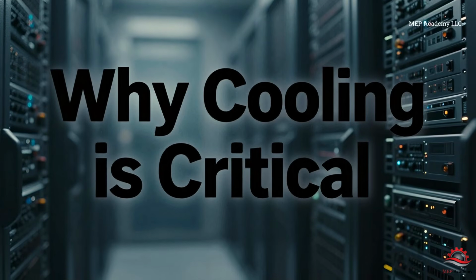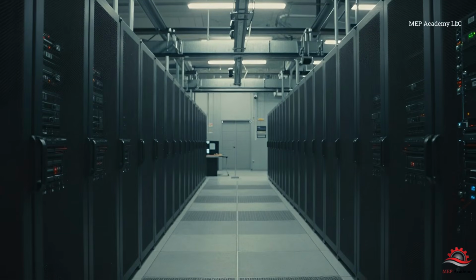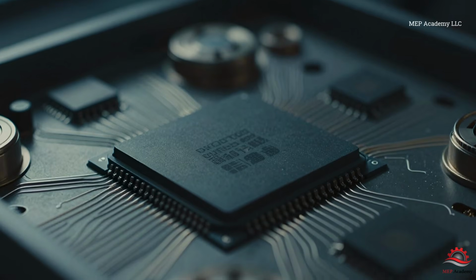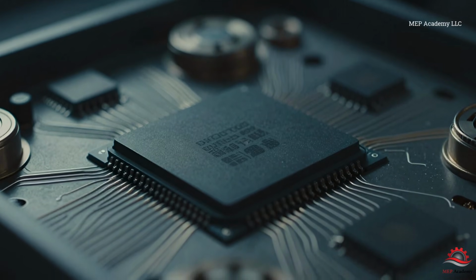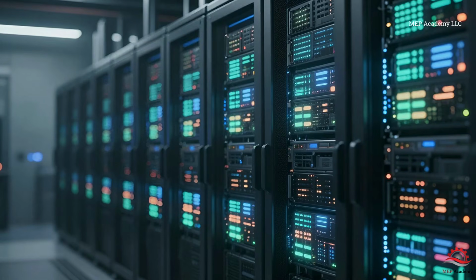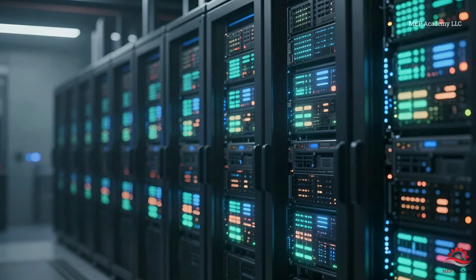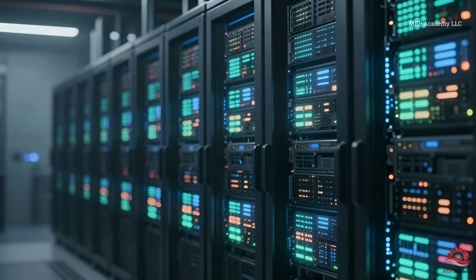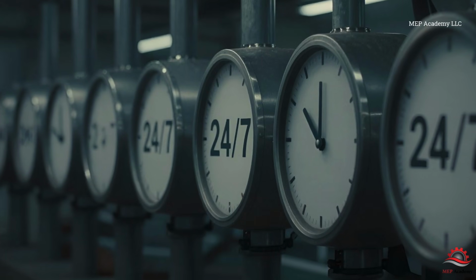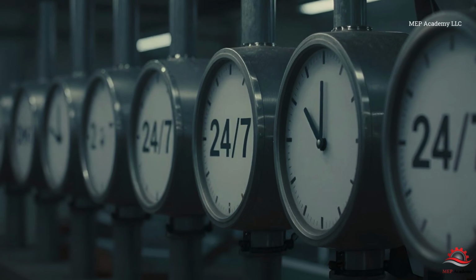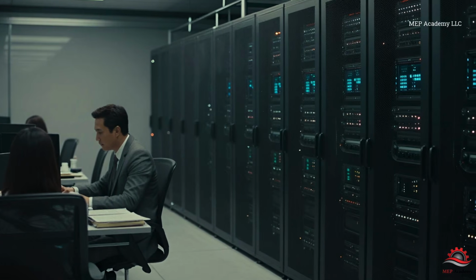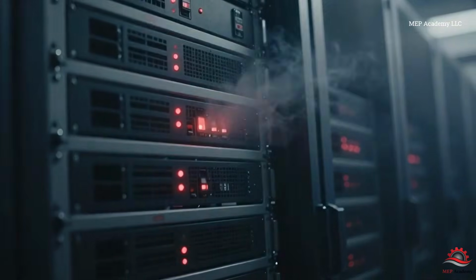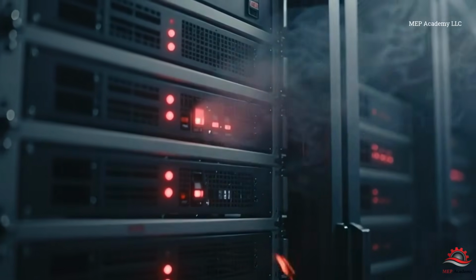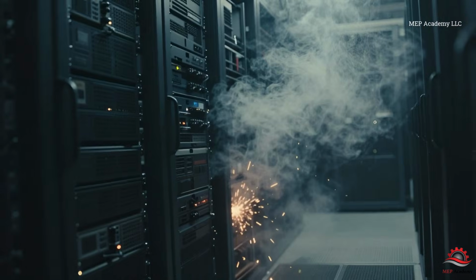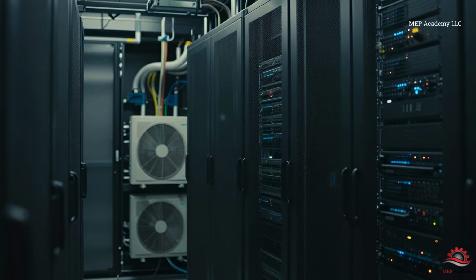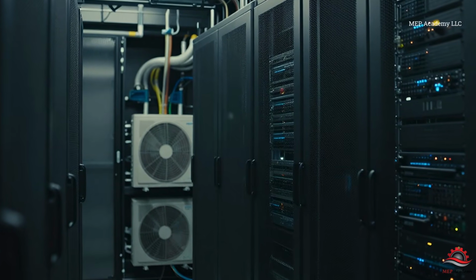Why cooling is critical. Let's start with the big picture. Every piece of IT equipment generates heat, and not a small amount. Modern data centers, especially those supporting AI and high-density loads, can generate enormous heat loads measured in megawatts. That heat must be removed continuously, 24/7, without interruption. Because unlike an office building, there is no tolerance for temperature swings. Even a small failure in cooling can lead to equipment throttling, system shutdowns, or catastrophic failure. So the cooling system isn't just supporting the data center, it's protecting it.